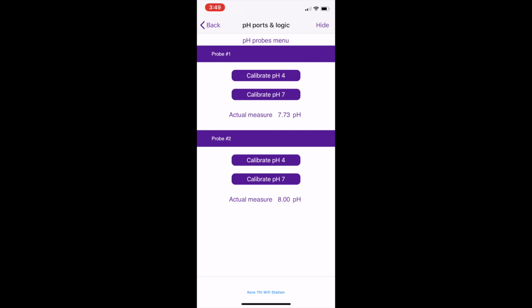It's really easy to calibrate the pH probes. You simply soak the pH probe in the provided bottles of calibration fluid that come with the Kore7th, and depending on which bottle you're using, you would press the Calibrate pH 4 or Calibrate pH 7 option. I recommend soaking the pH probe for a good 5 minutes to allow it to stabilize before calibrating. Pacific Sun recommends that you do pH 4 and then do pH 7, so that's the order you should calibrate in.